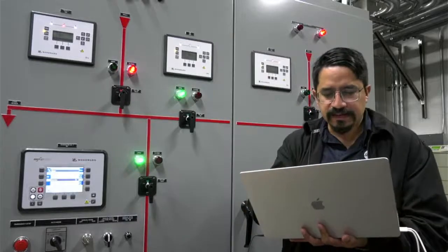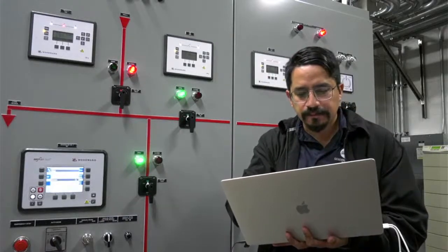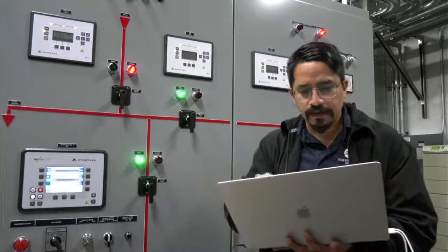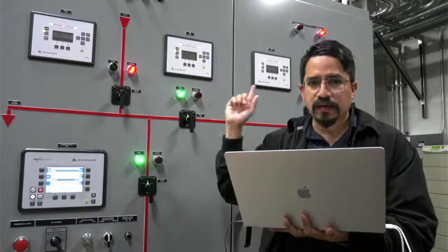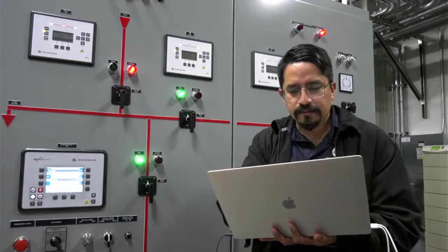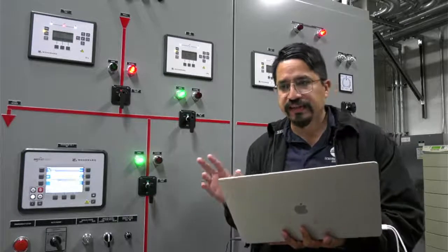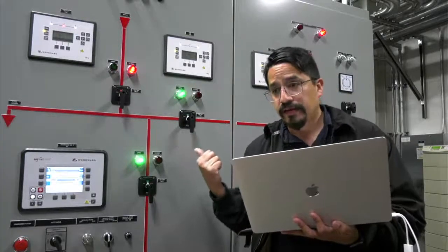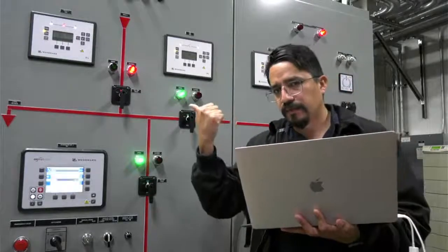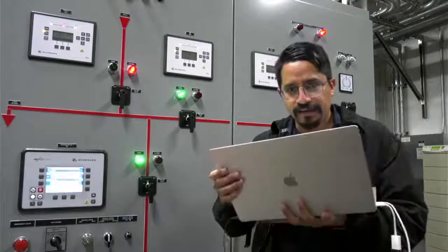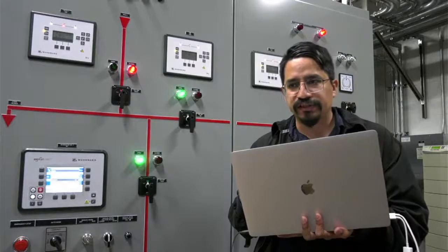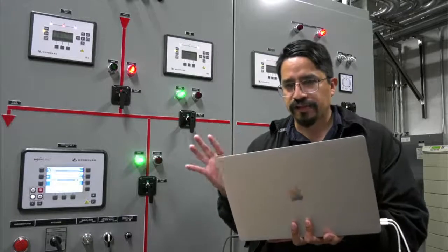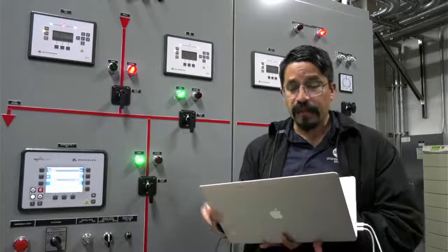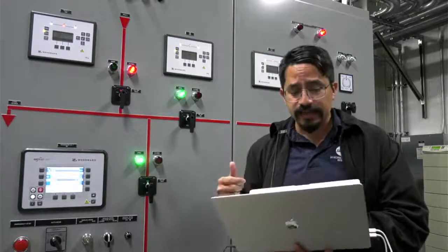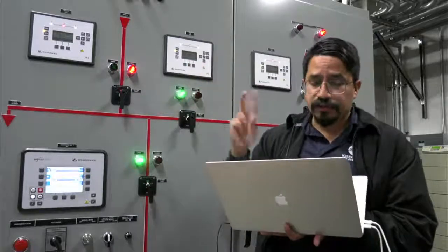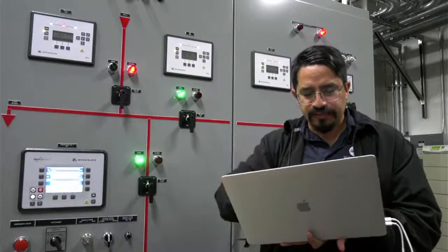So, following the table, it says that basically the system is in auto, and both TICO fail. So the condition is that the circuit breakers are not locked out. The circuit breakers are the ones on the back that we saw a moment ago. They have to be healthy and operating in normal conditions, and that's one of the conditions for the auto to be working. If that flag is okay, and we lost the two TICOs, we're gonna follow this procedure.